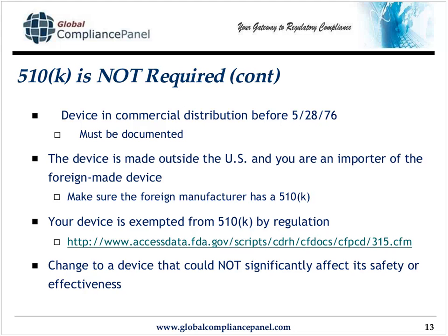There are some devices that are exempt from 510K by regulation, and here's the location to those. And when you find your device, make sure it says exempt from pre-market notification submission, and therefore no 510K is required. And last, a 510K is not required if you change your device, and the change cannot significantly affect the device's safety or effectiveness.